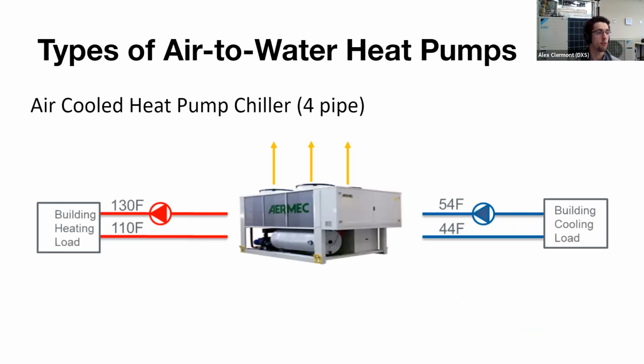Now these can also be 4-pipe machines, where they can actually do heating and cooling all in one machine. So they're starting to be common as well, 4-pipe air source heat pump machines. Some pros and cons of these bigger air to water heat pump machines. If you're using an air source heat pump chiller that will feed fan coils, as we previously discussed, you have to decide, does this machine need to be 2-pipe as a changeover system, or can it be 4-pipe? Does it need to be 4-pipe for simultaneous operation?